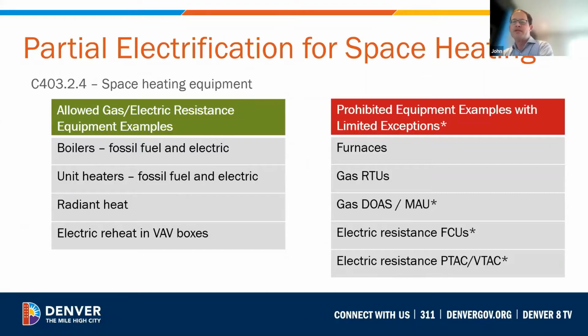The code limits the use of heating systems that use fossil fuel equipment. Some equipment, such as central boilers for space heating, are allowed. As of January 1st, natural gas heating is no longer allowed in rooftop units and gas furnaces. Electric resistance heating is restricted in systems such as smaller PTAC zonal systems. Some electric resistance heating is allowed as reheat for systems that use VAV reheat systems for air distribution.